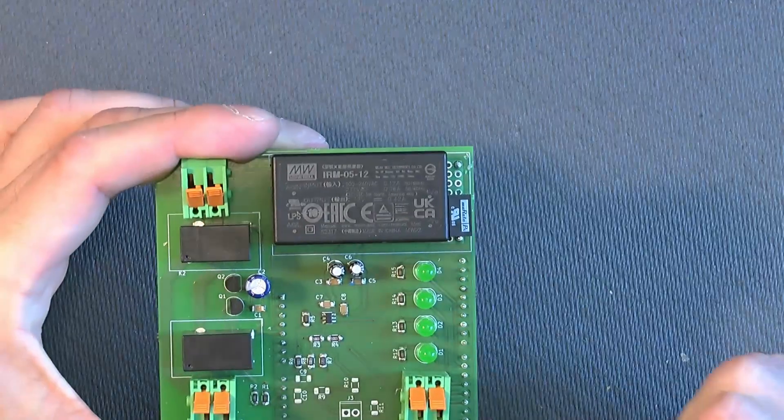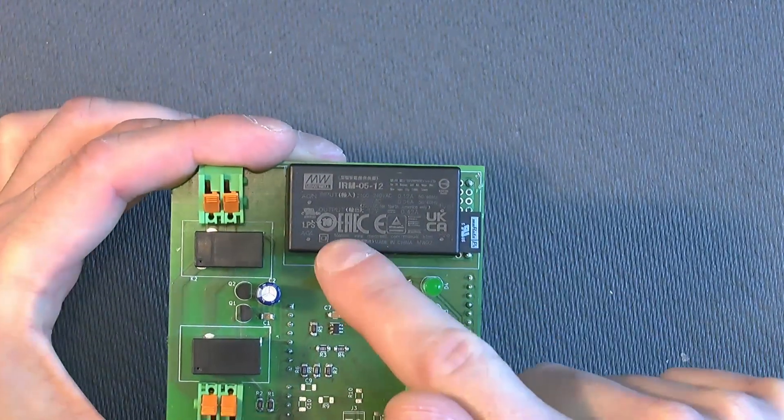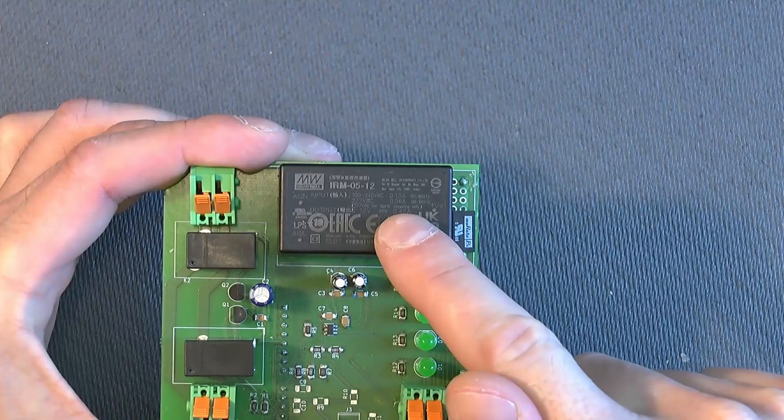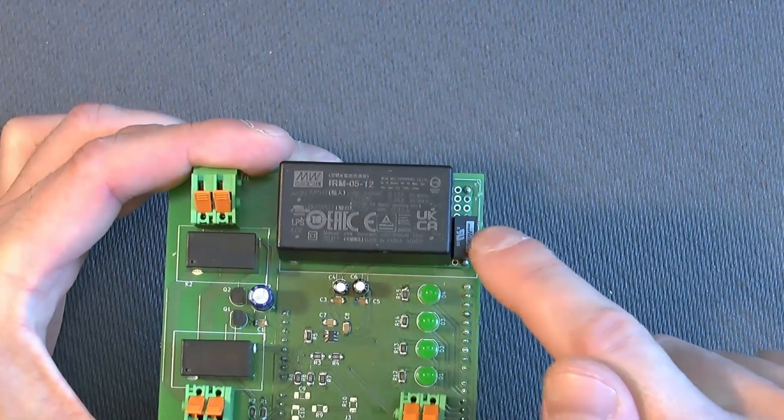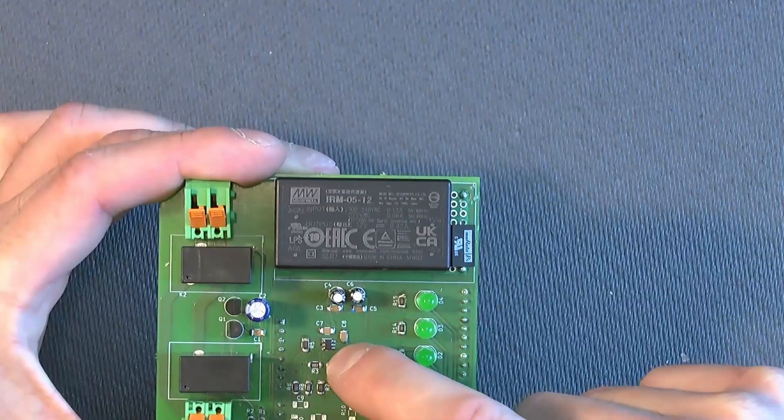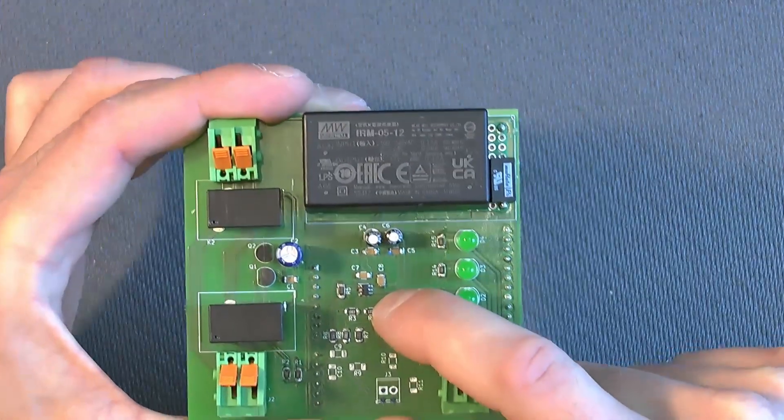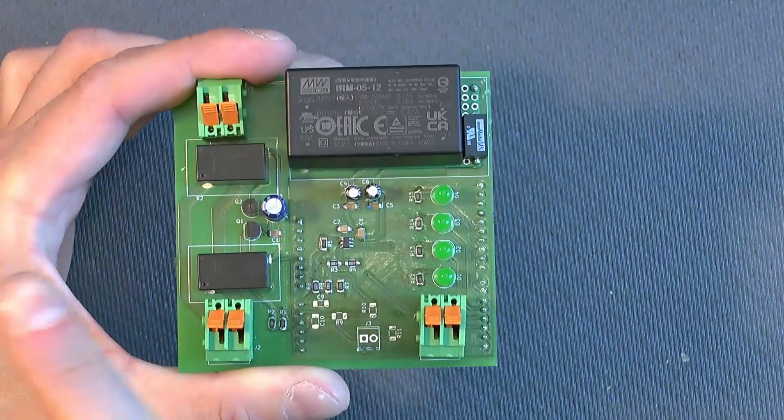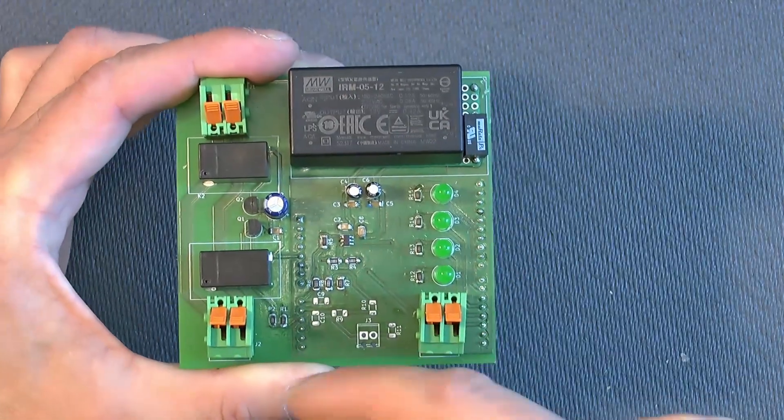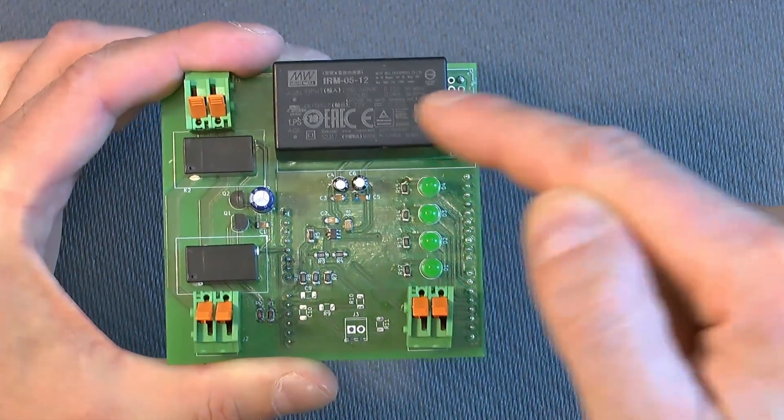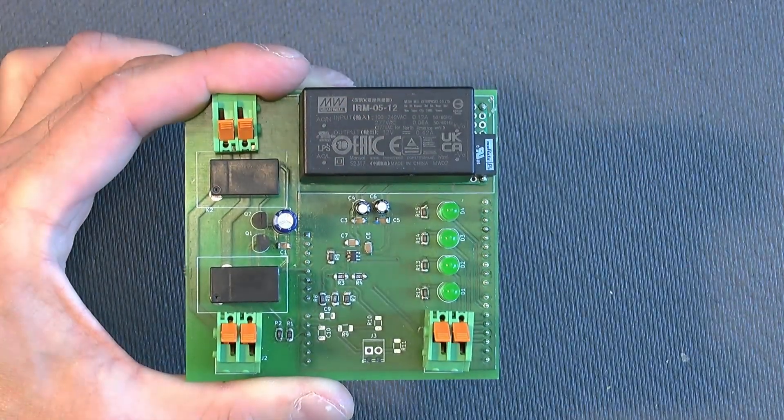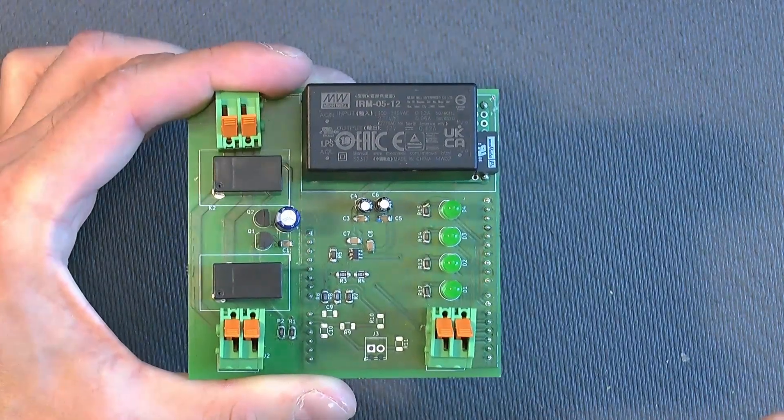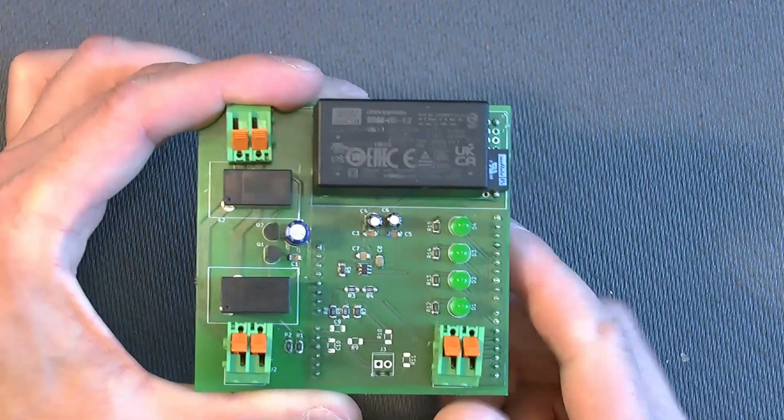Then we have a power supply here and another one here. This one converts 230 volts into 12 volts. And this one converts 12 volts into minus 12 volts. And we need this because we have an amplifier here that works as a comparator. That is the one that is gonna help us produce the PWM, which is the control pilot. It will go to plus 12 volts and minus 12 volts and back a thousand times per second because it's a one kilohertz signal.